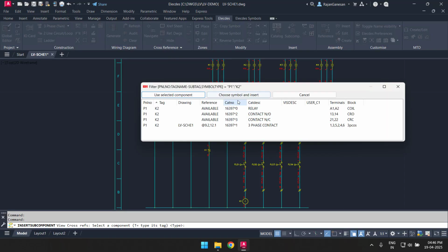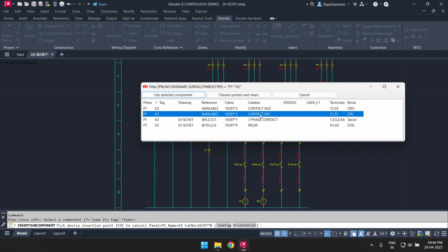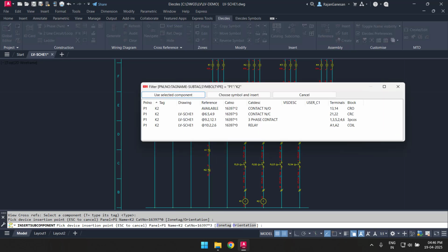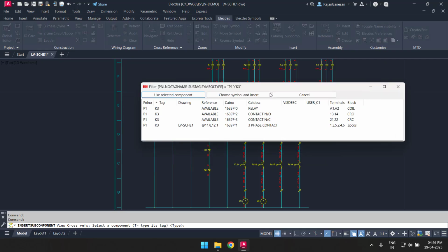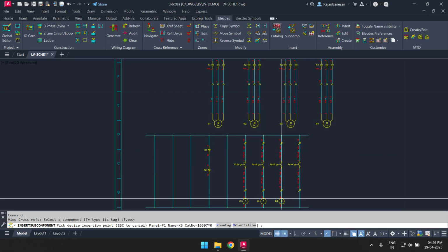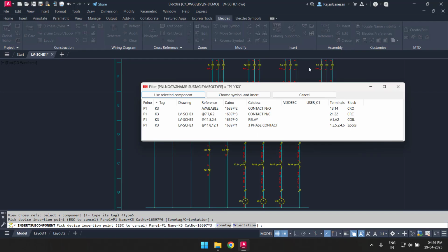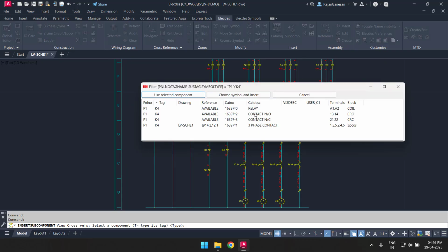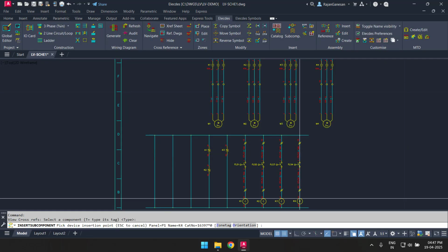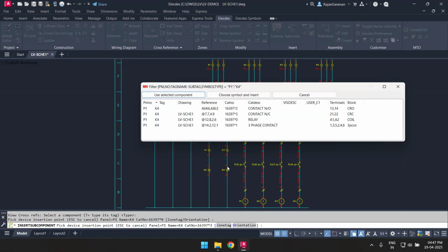The Elecdes system for managing subcomponents is extremely useful when managing complex protection control relays for larger equipment and higher voltages. When tasked with drawing up a protection and control relay with 30 family members and 60 terminals, it pays to be accurate and to manage your contacts' terminals. Without Elecdes, these types of relays are managed manually, and errors will be highly likely and will cost both production time and rework time.